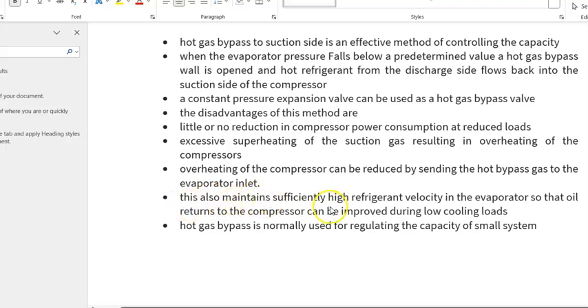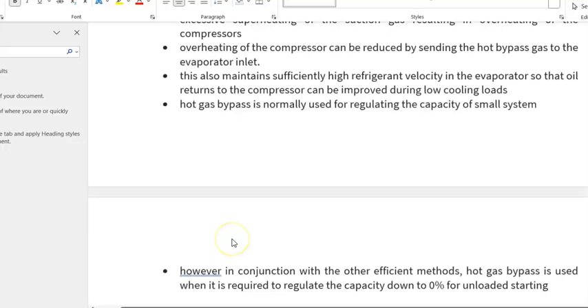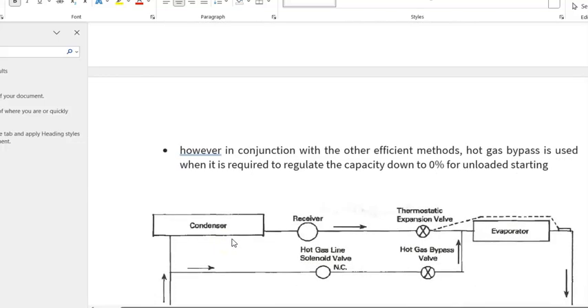This also maintains sufficiently high refrigerant velocity in the evaporator so that oil return to the compressor can be improved during low cooling loads. However, in conjunction with other efficient methods, hot gas bypass is used when it is required to regulate the capacity down to zero, or for unloaded starting.